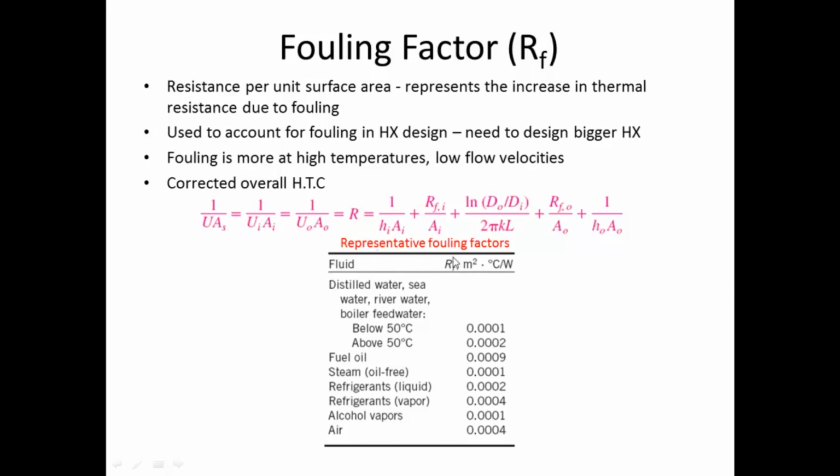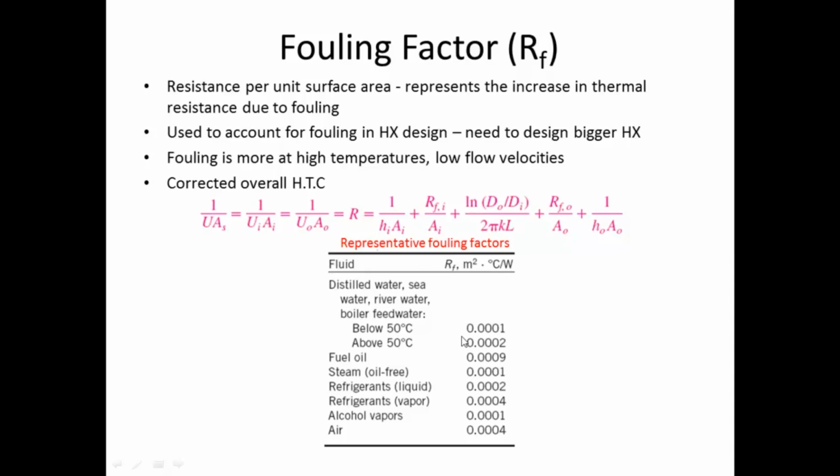Some representative fouling factors are given here. Here again we can see some interesting facts such as the effect of temperature. We have seen that at higher temperatures the effect of fouling is more, that is denoted by the difference in the fouling factor for the two temperatures here. Also in cases where there are more chances for sediment such as fuel oil, we have a higher value of the fouling factor RF.